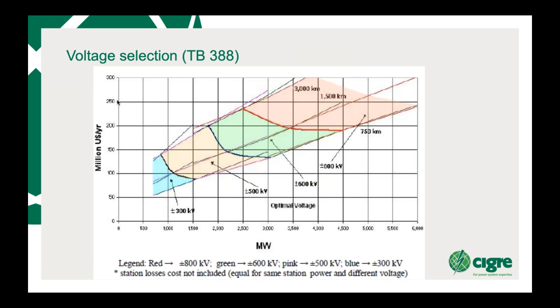Say, for example, you want to transfer 3000 megawatts down 1500 kilometers, it would end up in the green area, which will then give you 600 kV. If you wish to use 4000 megawatts for 1500 kilometers, you're then looking at the 800 kV area. And they have in China built an 800 kV DC, and they're looking at 1100 kV DC right now.